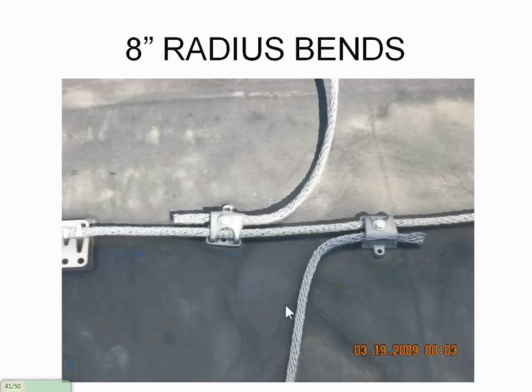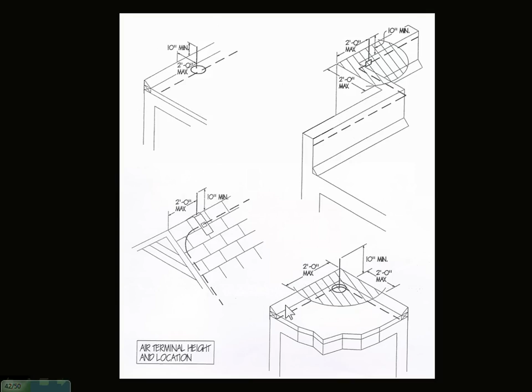So these are good diagrams of where you need to put the air terminals. Basically, it shows everything. You have to be 10 inches above the object that you're trying to protect. You have to be within 2 feet of the outside corners. You have to be within 2 feet of the outside ridges. And then these diagrams show you how to do it on a parapet, a flat roof, a ridge, and then the corner.